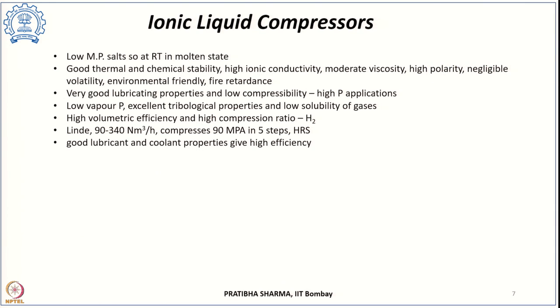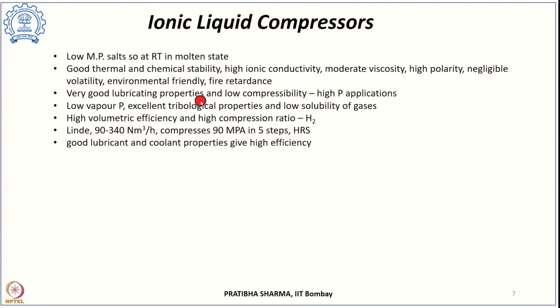Another type is the ionic liquid compressor. These are liquid compressors but the liquid used is an ionic liquid, which is a low melting point salt that is present in its molten state at room temperature. These ionic liquids have several advantages: very good thermal and chemical stability, high ionic conductivity, moderate viscosity, high polarity, and negligible volatility, which minimizes liquid loss. They are environmentally friendly, fire retardant, and have very good lubricating properties that reduce associated friction, wear, and leakages.